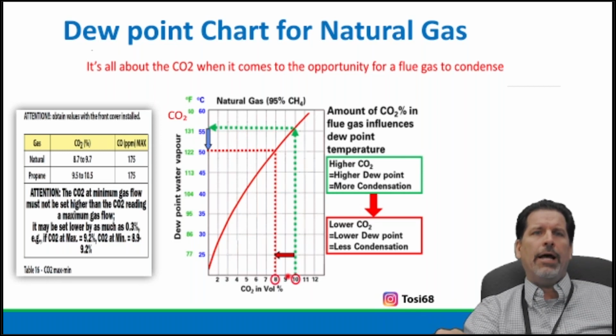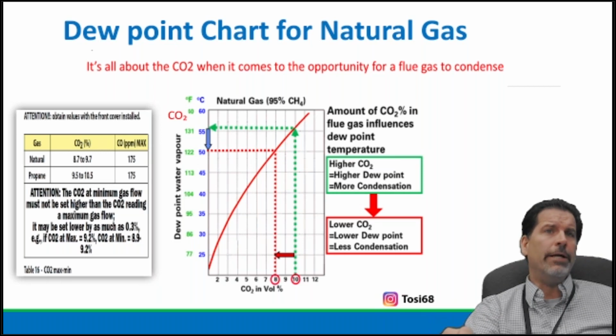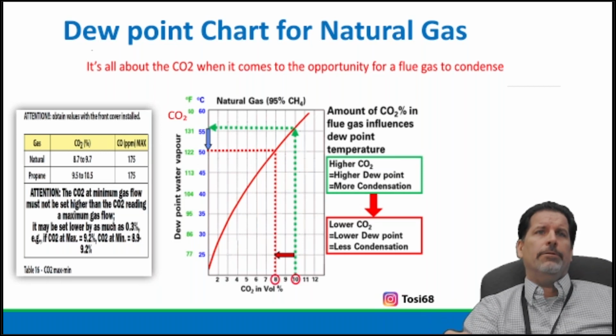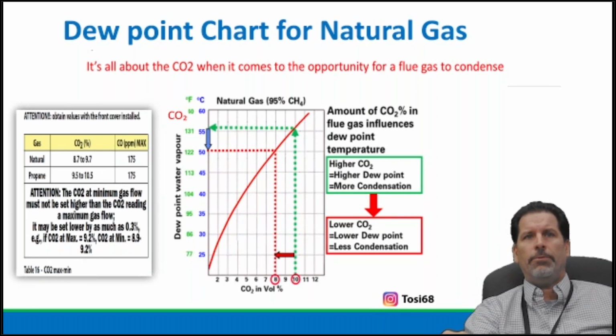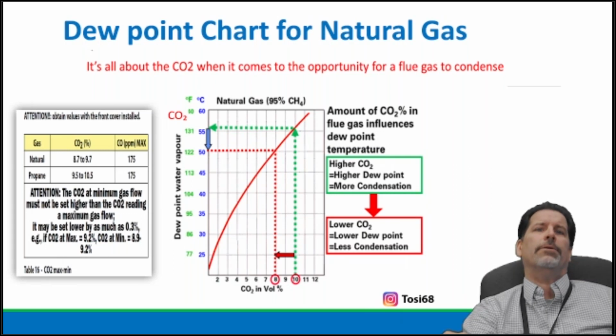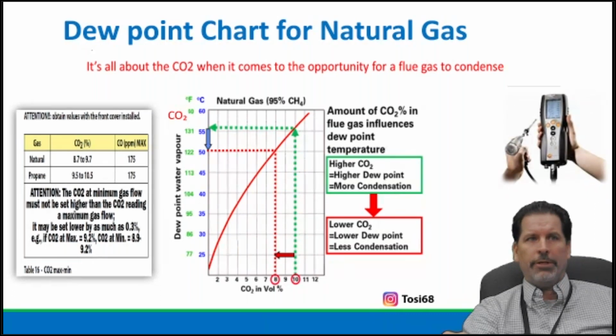If we were to change our 9 to something lower, lower CO2, right? Then we don't start condensing until we go even lower, 122. So understanding that gap is time and energy wasted, right? We want to condense as soon as we can. So understanding what the CO2 represents in setting up the calibration of our gas valve, that combustion: air, fuel, and a spark, right? That's the 3 components we need for combustion, right? So it's all about CO2 when it comes to opportunities for flue gas and condensing, collapsing our vapor back to a liquid, using a combustion analyzer.